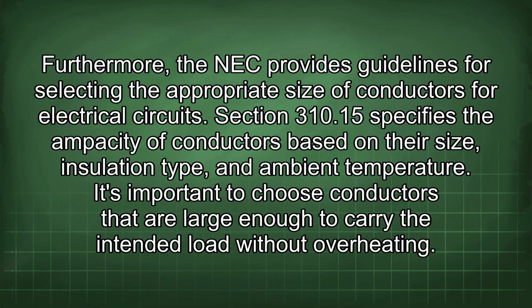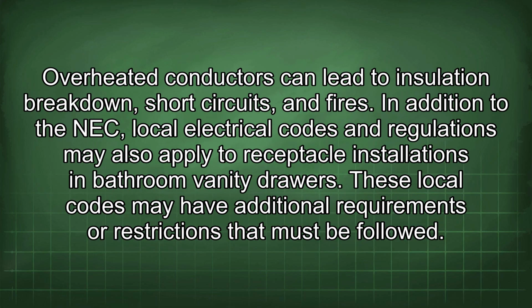Furthermore, the NEC provides guidelines for selecting the appropriate size of conductors for electrical circuits. Section 310.15 specifies the ampacity of conductors based on their size, insulation type, and ambient temperature. It's important to choose conductors that are large enough to carry the intended load without overheating. Overheated conductors can lead to insulation breakdown, short circuits, and fires.